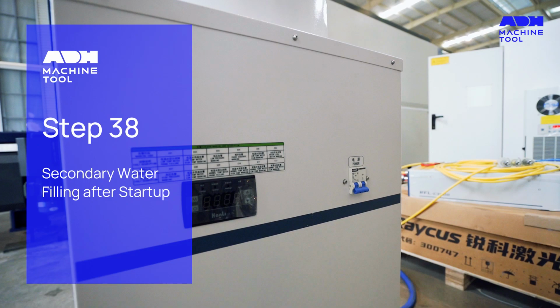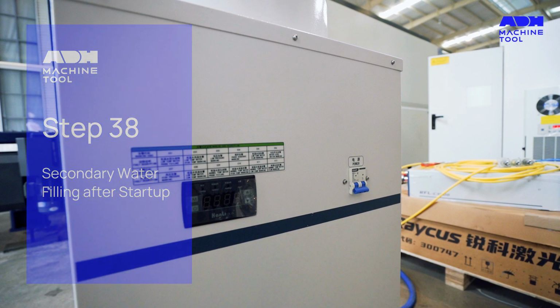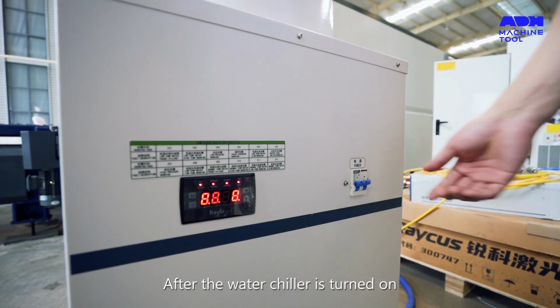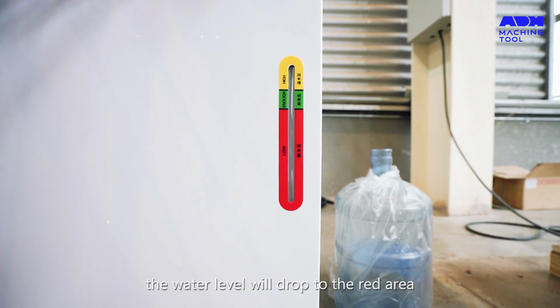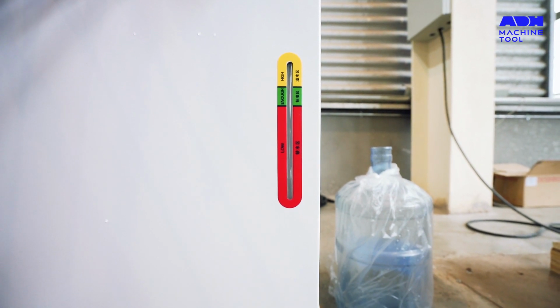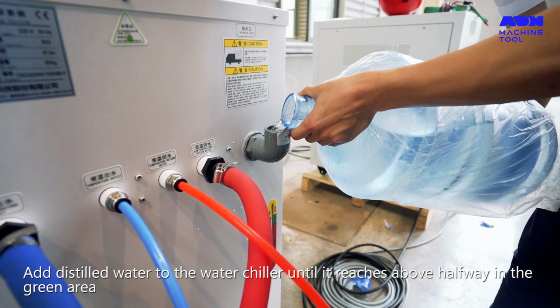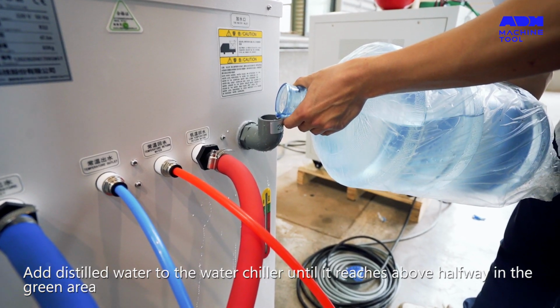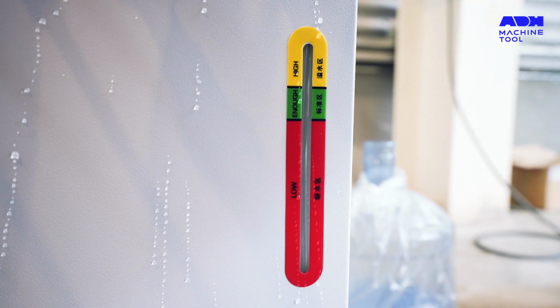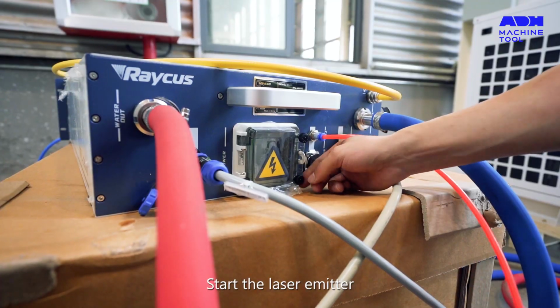Step 38. Secondary water filling after startup. After the water chiller is turned on, the water level will drop to the red area. Add distilled water to the water chiller until it reaches above halfway in the green area. Start the laser emitter.